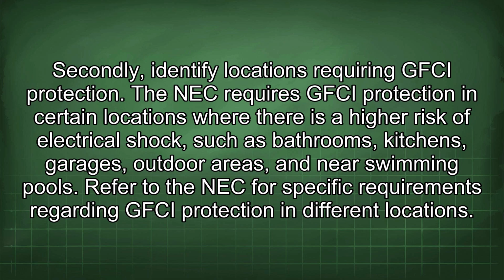Secondly, identify locations requiring GFCI protection. The NEC requires GFCI protection in certain locations where there is a higher risk of electrical shock, such as bathrooms, kitchens, garages, outdoor areas, and near swimming pools. Refer to the NEC for specific requirements regarding GFCI protection in different locations.